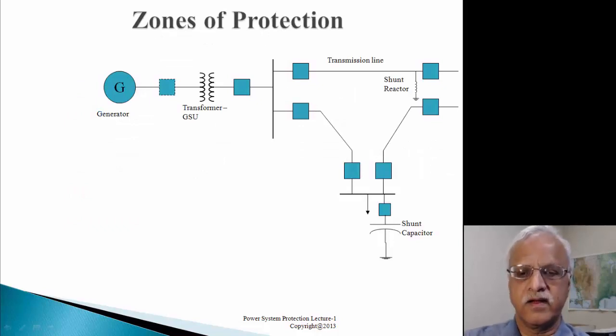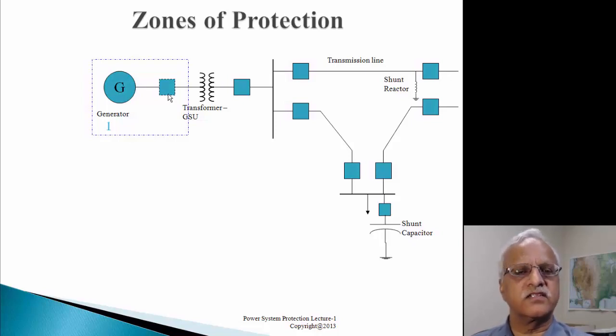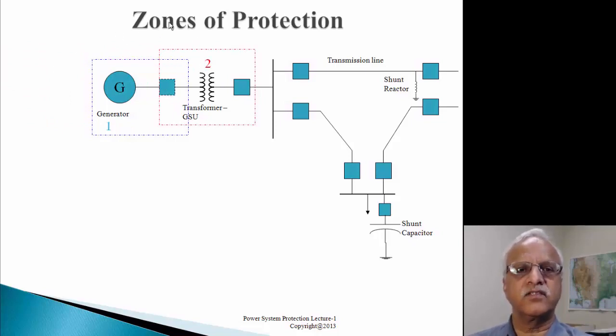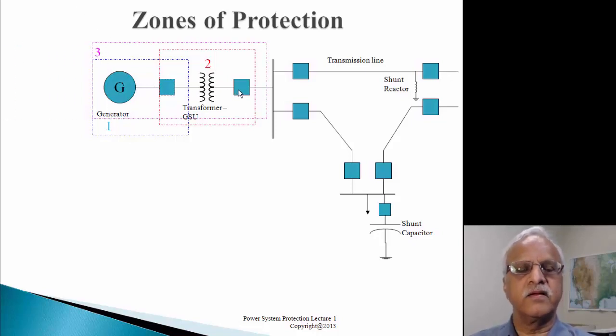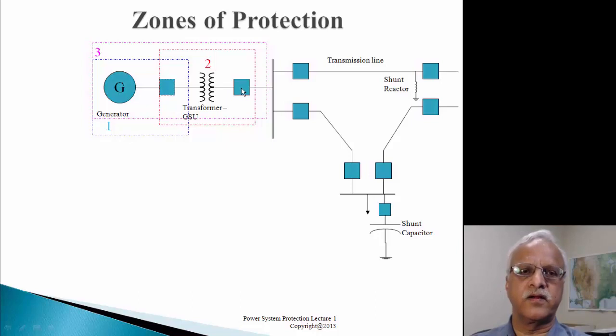Looking at a protection scheme: if there is a fault in the generator, we need to open only one particular breaker that isolates the generator. Similarly, if we have a fault in the transformer, we have to open two breakers - one on the low side and one on the high side. If protection covers both generator and transformer, we trip the high side breaker of the transformer, and if we have a low side breaker, we can trip that too.